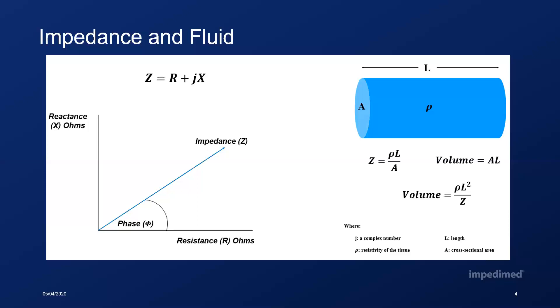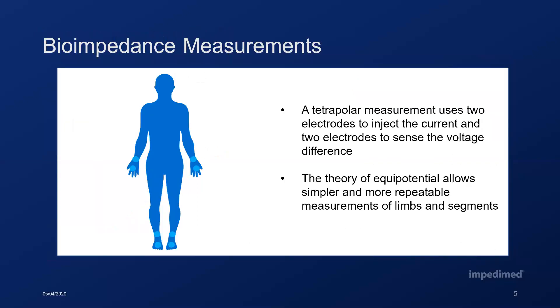So how do we take bioimpedance measurements? A tetrapolar measurement uses four electrodes to measure the impedance, minimizing errors introduced from contact impedance by separating the drive and sensing electrodes. Electrodes can be gel-based or plate electrodes and are the interface between the body and the bioimpedance device. To measure the whole body, we drive the current on the hand and foot and sense the voltage or impedance between separate sensing electrodes on the wrist and ankle. The current flows between the hand and foot in black, and the voltage is sensed between the wrist and ankle in green. The part where the green and black overlap is what is measured — so between the wrist and the ankle.